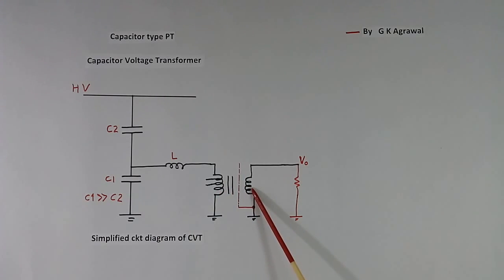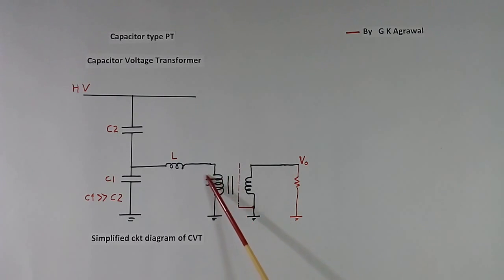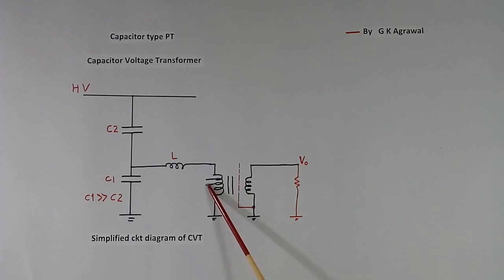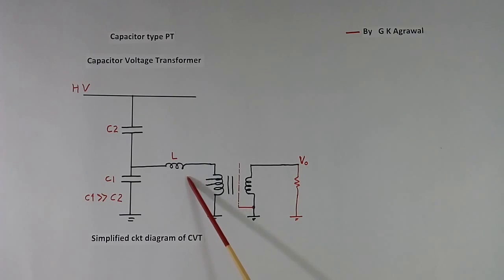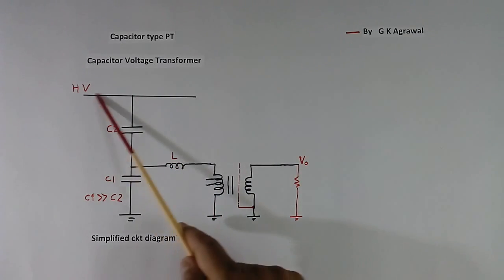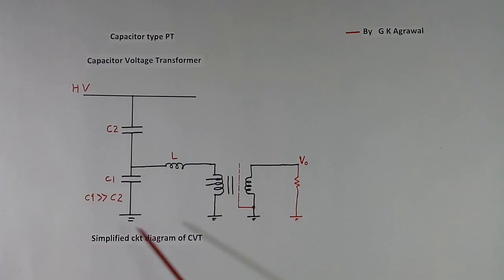Here I have shown one isolating PT, but this is a low voltage type — there is no high voltage winding. The load is connected to the secondary. The red dotted line shown is a shield for noise, also called a Faraday shield. This is the core. In the primary I have shown 2-3 wires — suppose the primary has 100 turns, they will take connections at 99, 98, or 97 turns to correct the ratio if there is any error. This is called tapping. There is also an inductor to compensate the phase shift. In very high voltage applications, due to lower cost, capacitor type PTs are used. This also has one more application in PLC — power line carrier — used for communication.